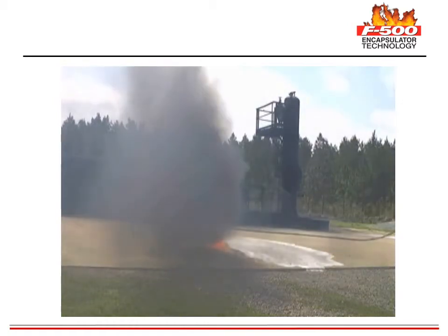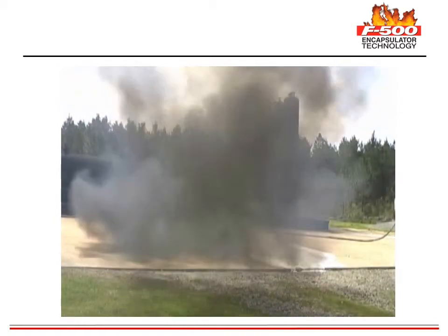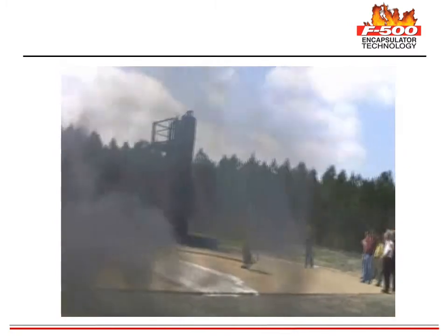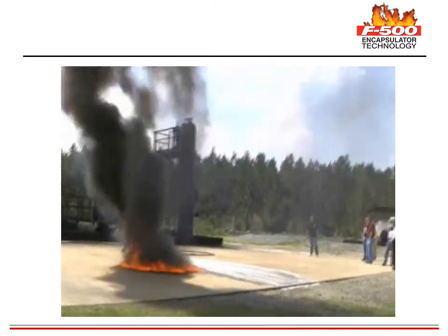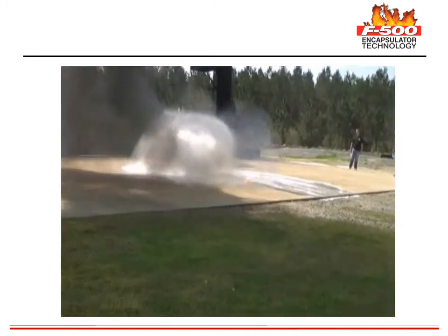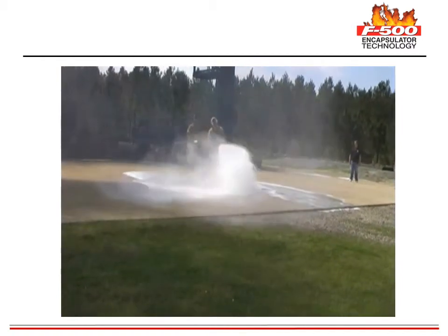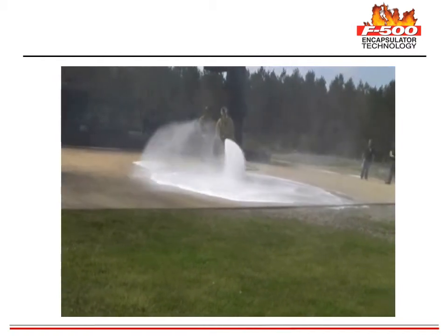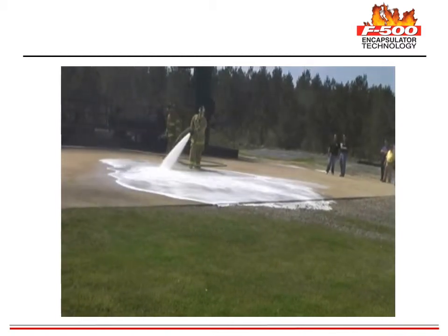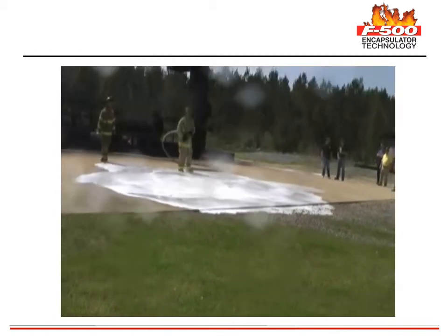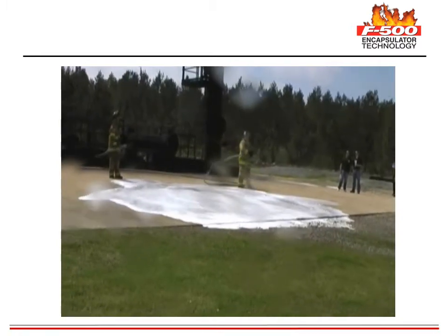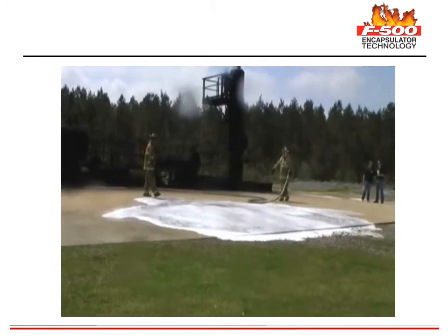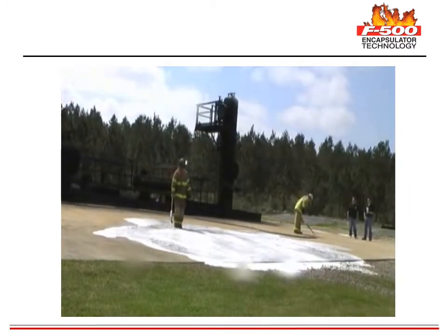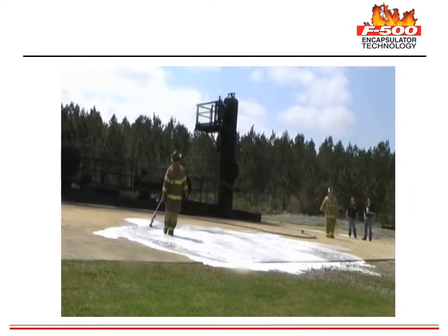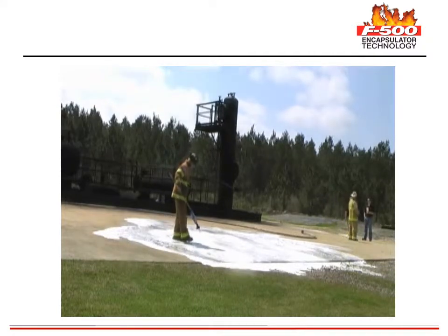This demonstration shows a large gasoline spill. Half is treated with 3% F500 solution. Flame is applied but only ignites the non-treated area. Then the fire is extinguished using a dispersed spray pattern sweeping over the surface. The F500 encapsulates the gasoline vapor molecules, rendering them instantly non-flammable and non-ignitable. You will notice at one point the firefighter with the torch will disperse the F500 solution on the ground without any reignition. If this were foam, the gasoline would have reignited where he kicked the foam aside, because foam only lays on the surface and does not encapsulate.